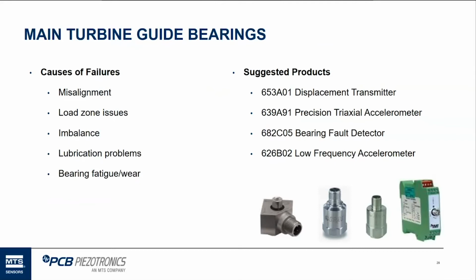We have a displacement transmitter that's going to look at bearing displacement, and a triaxial accelerometer that can look at all three: horizontal, vertical, and axial vibration. We've got a very, very cool bearing fault detector sensor, also a transmitter, that can look specifically at the frequency that bearing faults typically occur in and provide feedback on that. And also we have a low frequency accelerometer, which is great for looking at slower speeds and slower speed related problems on the main turbine guide bearing.